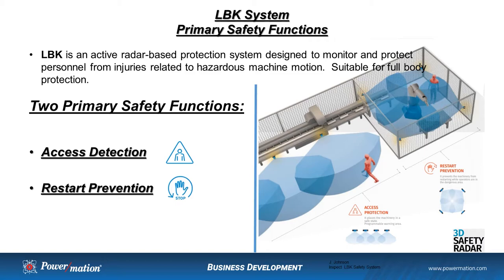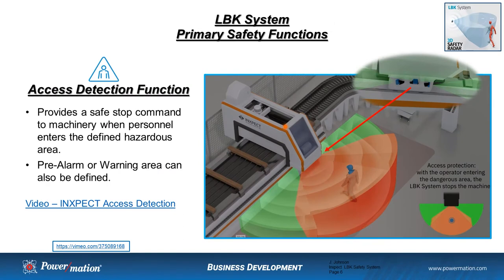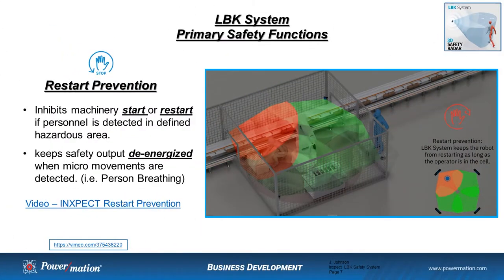It's important to keep in mind that this is for full body protection. This is not finger protection, hand protection, or foot protection. This is a full body protection system. The two primary safety functions this system is designed to accomplish are access detection and restart prevention. Very similar to the laser scanner, access detection provides a safe stop command to machinery when personnel enters into the defined hazardous area. You can also provide a safe speed command when someone enters into the pre-alarm or warning area.